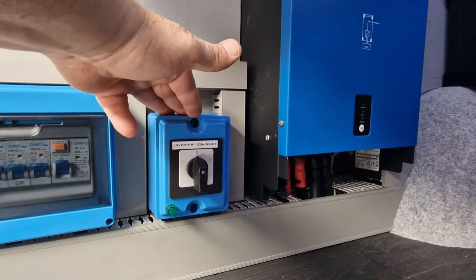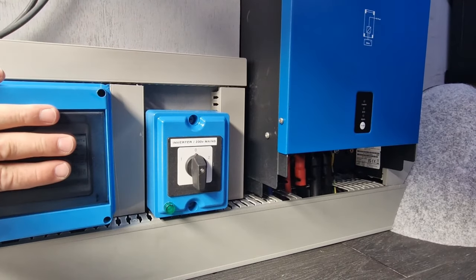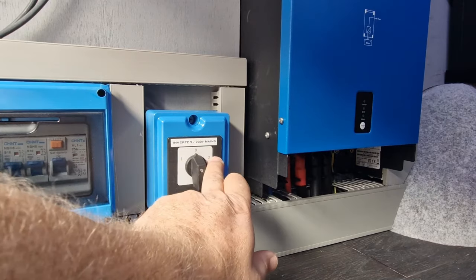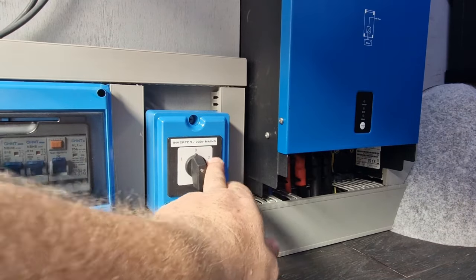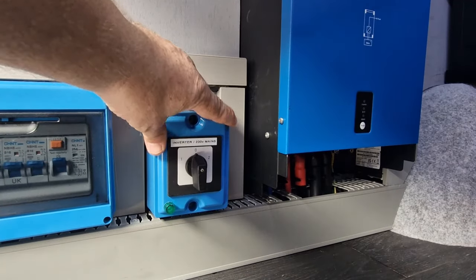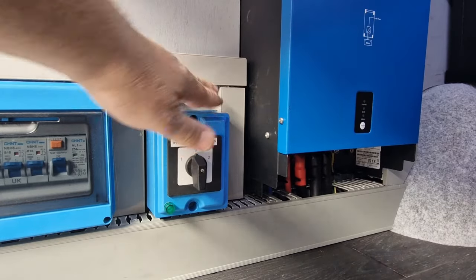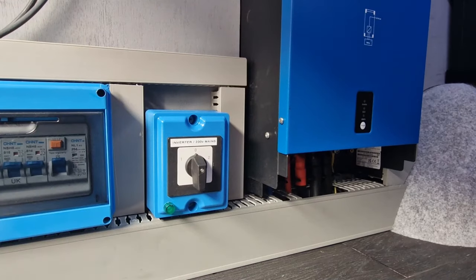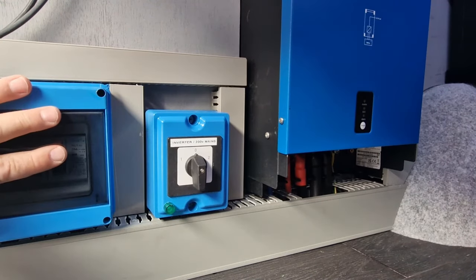You do all your dead checks, make sure everything is torqued and connected right and sized correctly, but you've got to have confidence in your work, and we've got to turn it on. Just to be safe, we don't want to energize anything beyond the inverter for now. We just want to get the inverter working, check the output, then turn it all back off. We'll be using the inverter isolator, a changeover switch that lets us decide where to supply our distribution board from: position one is inverter, position two is mains. This can also have our battery charger plugged into that side. Position zero means no power at all is coming to it, isolating this part of the system from where the power is generated. So I'm safe in the knowledge that there's no power going any further than the inverter.